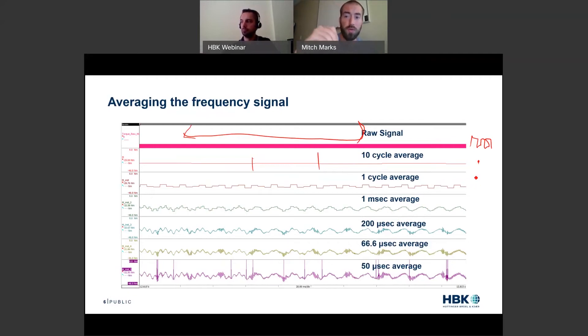We talked about how important having that time alignment is for accuracy. But we get this basically steady state value. Torque's not changing a whole lot here. Talk about torque ripple, there's none. This is a very steady state measurement we'd use for efficiency. If we look at just one cycle, one sine wave, we're going to see that this torque does bounce around a little bit. We get a bit of movement and we expect that. But it's still pretty steady state. We might use it for something like dynamic efficiency in a drive cycle test.